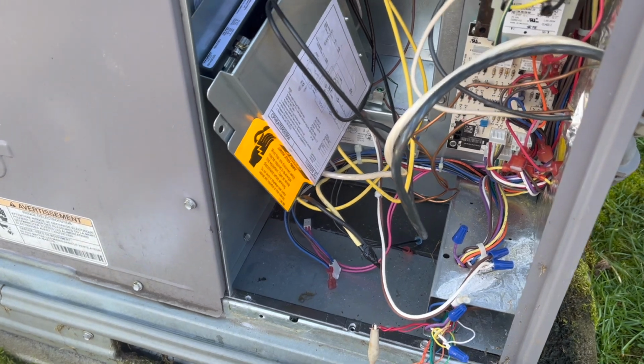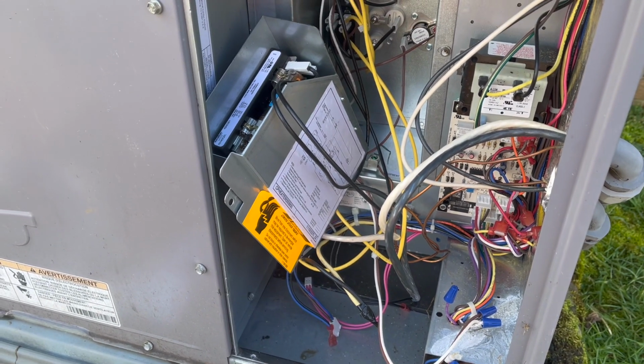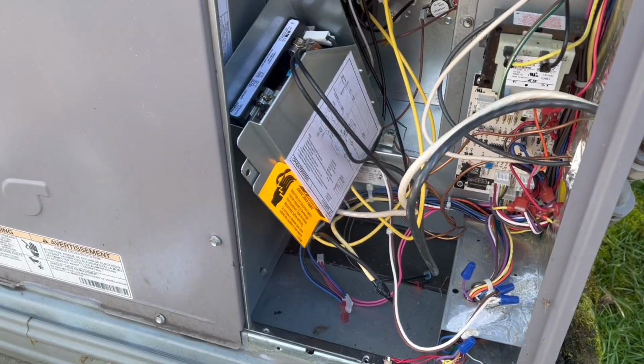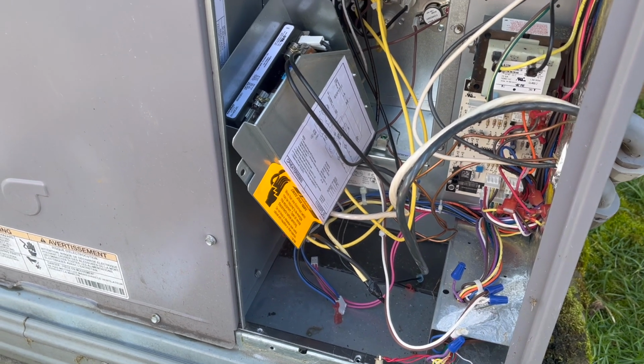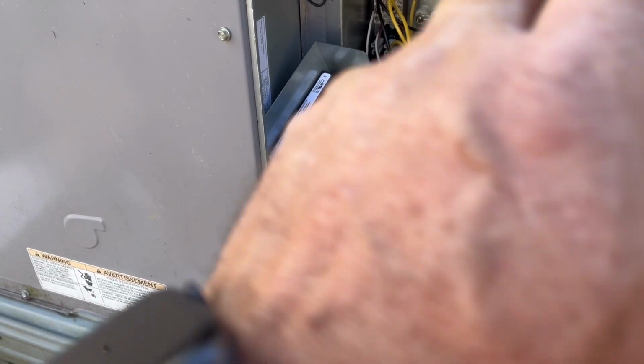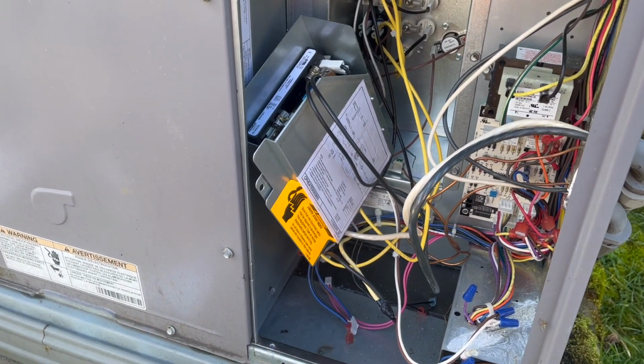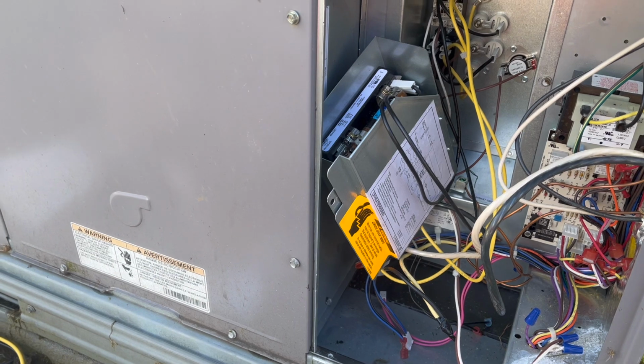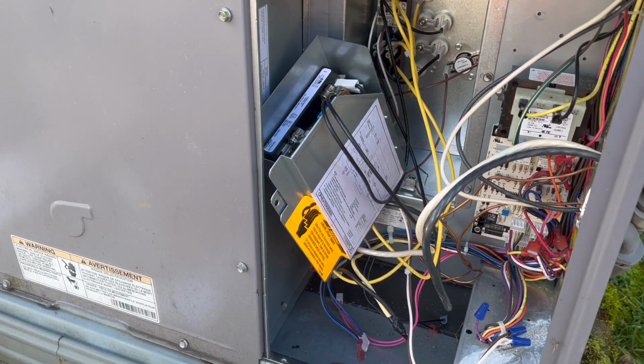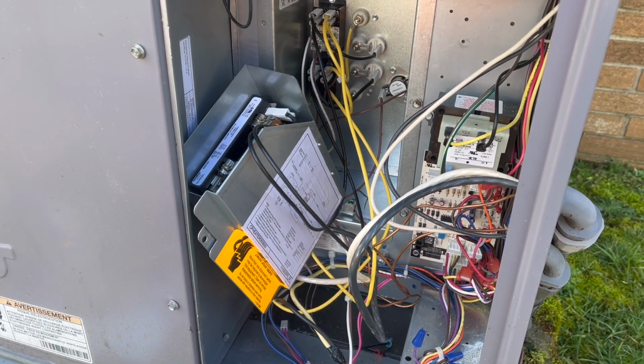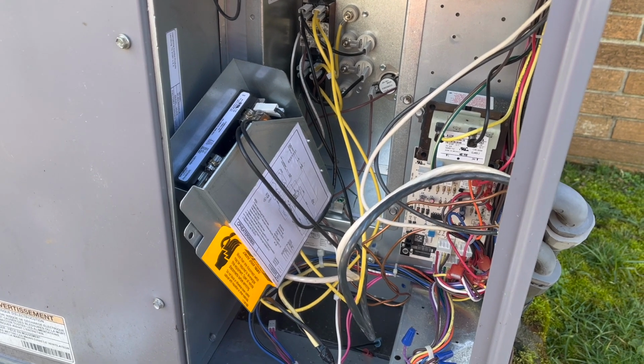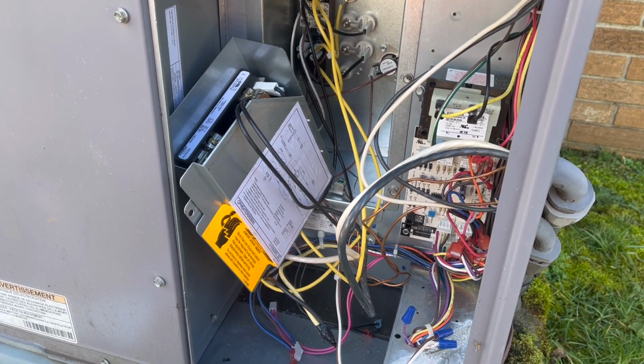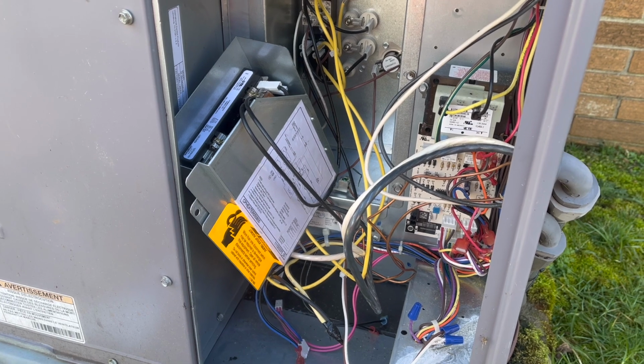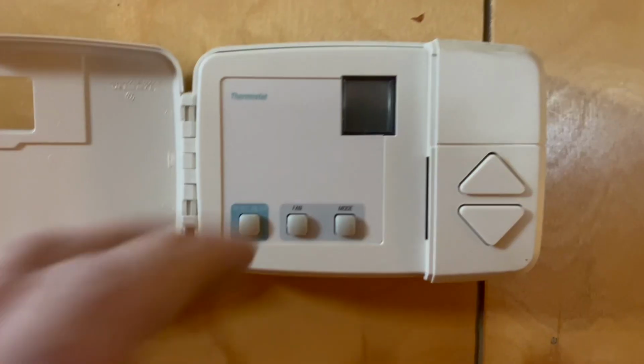More than likely it's got the old original Carrier thermostat that flipped open, and more than likely it's gone too. Like I say, I know the compressor and the fan came on outside for a few seconds before the fuse blew, and the indoor fan did come on and run fine when I tested it. So if the thermostat's good, we'll be ready to go. If it's not, surely I've got a thermostat on the truck. But I'll let you know. Yeah, she's deader than a doornail.